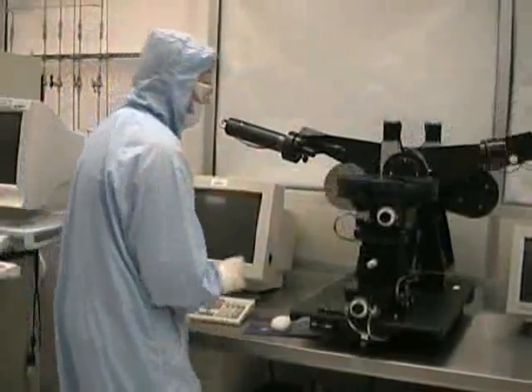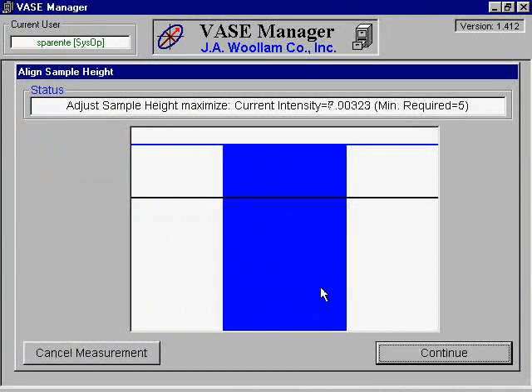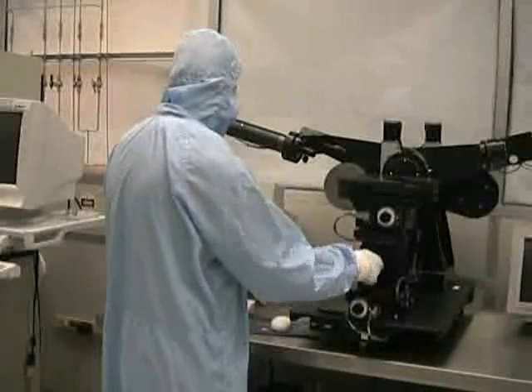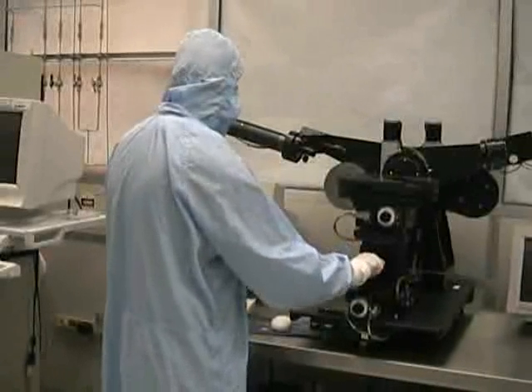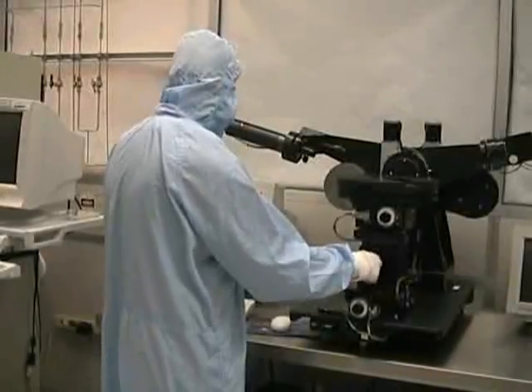For the next step, you should first make sure that the shutter lever is down and that the detector iris is open. You will need to adjust the intensity by rotating the height adjustment knob. Watch the blue bar and attempt to maximize the distance between the horizontal blue bar and the black bar by adjusting the knob. The intensity must be greater than 5 for the scan to take place. If it is still too low after adjusting the stage height, check again to make sure that the shutter on the analyzer is open. If the intensity is still too low, contact the MRC staff.